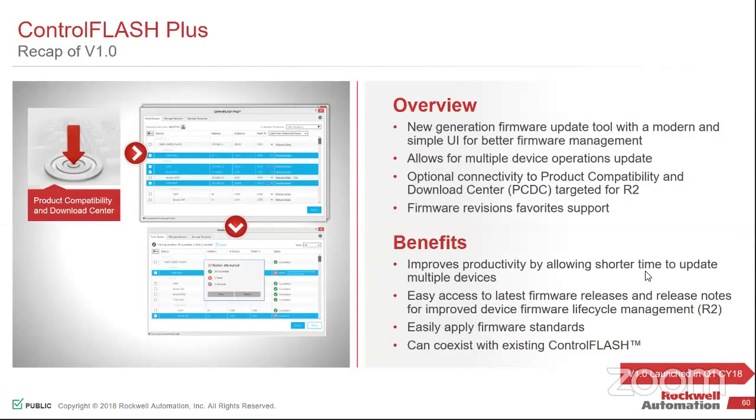So we can flash a whole rack or a whole chassis of I/O cards all at once, right? So we plug it all up, we plug our network card in, put the controller in, put whatever you want in this thing, and then say flash every single one of these to latest. It will take care of flashing them in the order that doesn't brick them, right? So it's not gonna halfway flash your controller and then start flashing the network card. We look both ways before we cross the street on that one. But it will go through it.